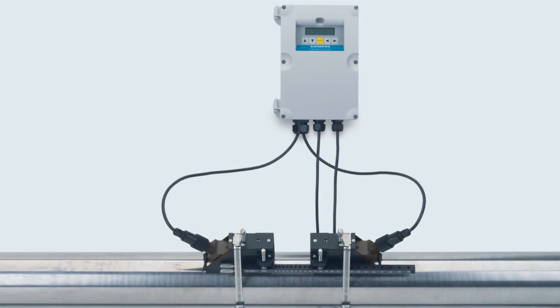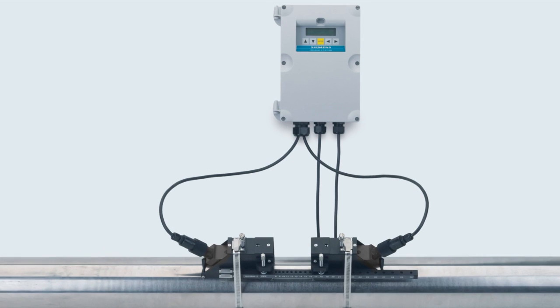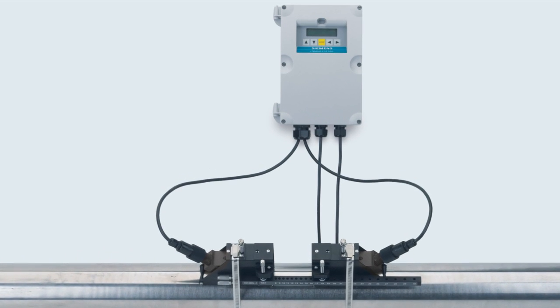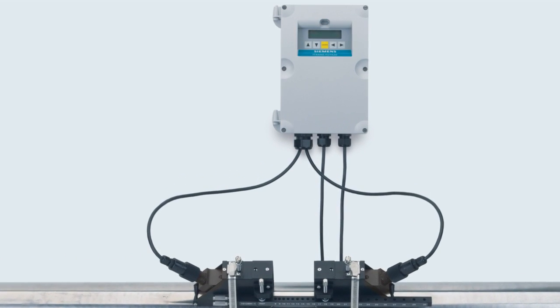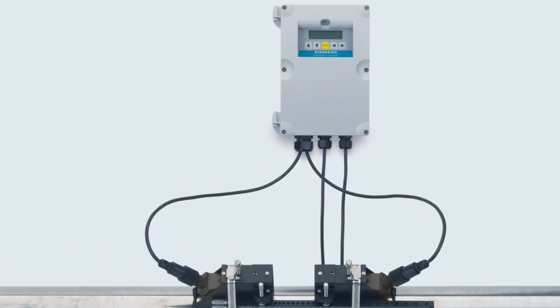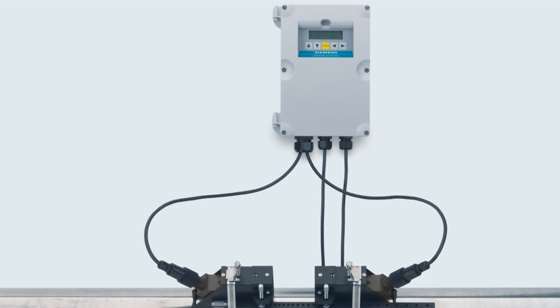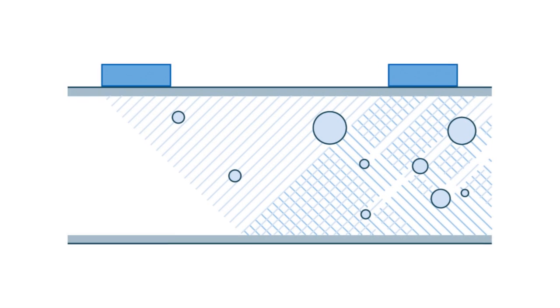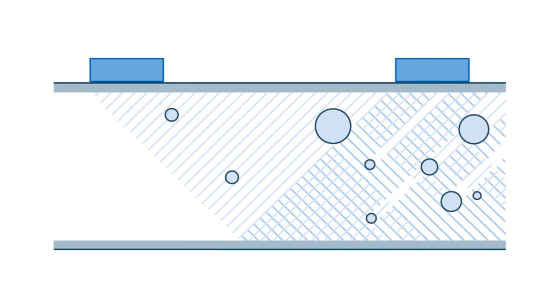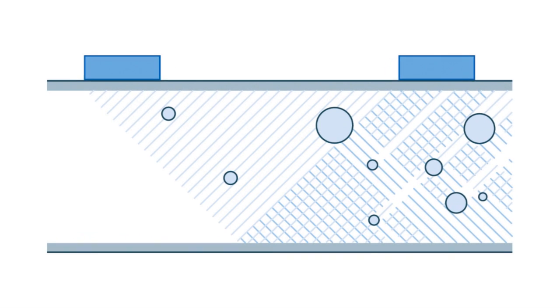The FST020 transmitter, combined with high-precision sensors, utilizes the same wide beam technology used in other Siemens clamp-on flow meters, which makes it possible to measure the flow of many different liquids, including those with moderate aeration or suspended solids. Today, we will review how easy it is to configure the FST020.